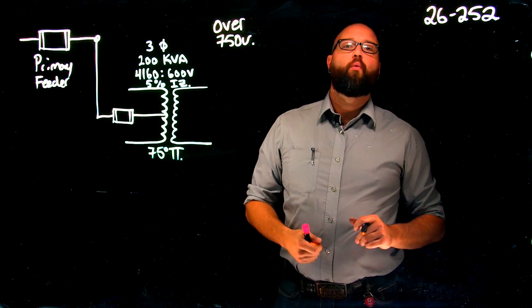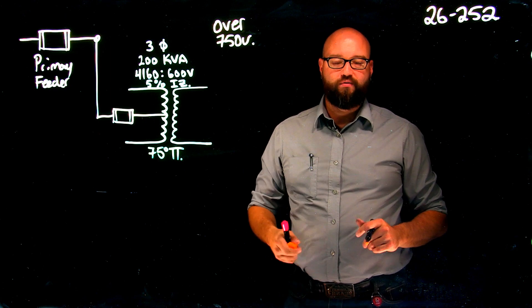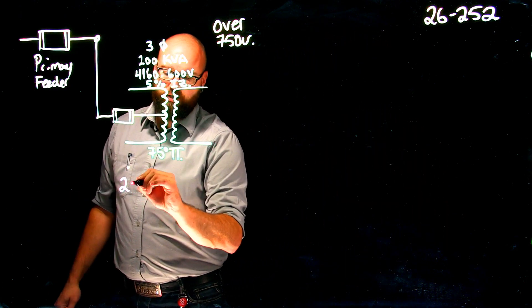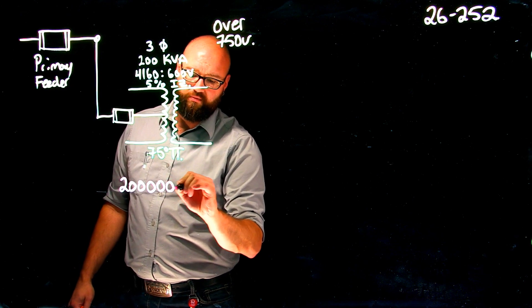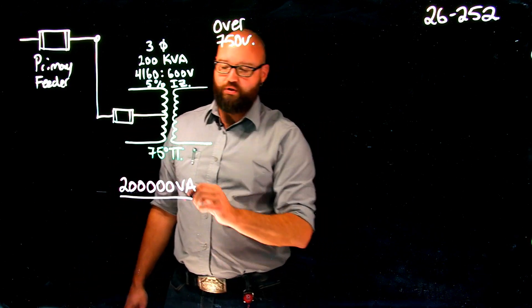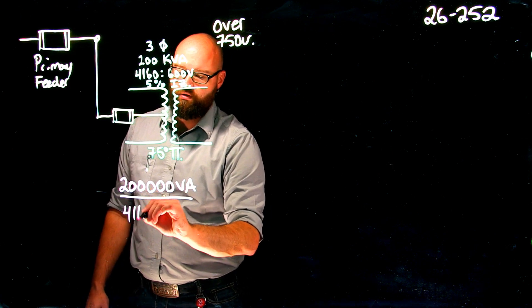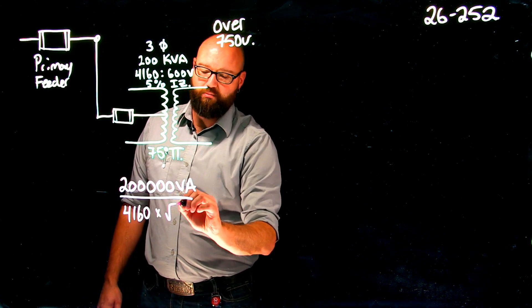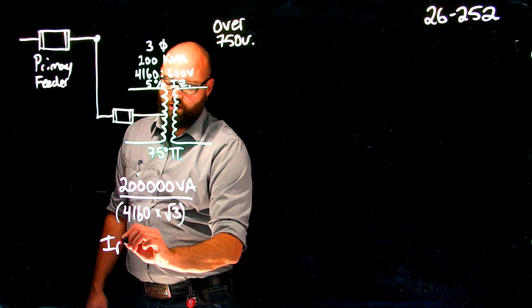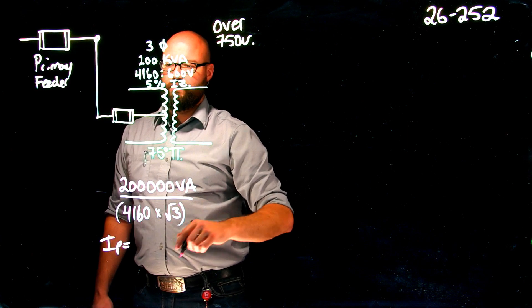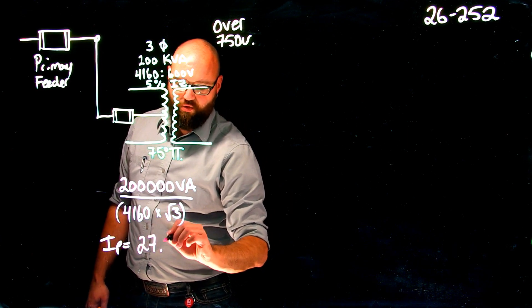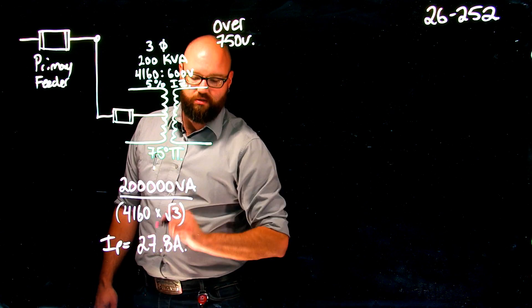First thing we need to figure out, what is the primary rated current on our transformer? As always, we're going to take our kVA, in this case 200,000 VA, divided by my line voltage of 4160 times root three, because this is a three phase transformer, gives me a rated primary current of around 27.8 amps.